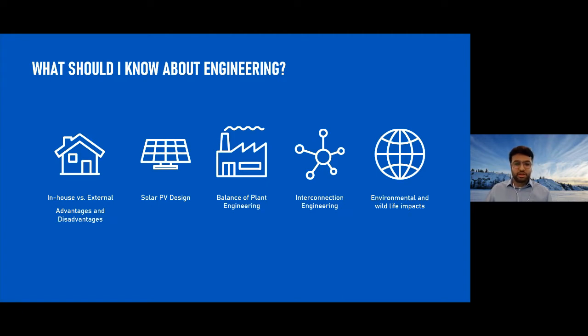Next, solar PV design. From a high level, depending on whether the application is residential, commercial, or industrial, solar engineering typically includes electrical design: the development of medium and low voltage single line diagrams, geo layouts, geotechnical surveys, civil foundations, piling, racking, earthworks, and traditional knowledge from the community in the design stages. Solar design considerations include selection of modules and inverters, module tilt angles, sizing the DC-AC ratio to avoid clipping losses, row spacing, system-specific losses including soiling losses, and whether the system will use fixed racking or trackers.